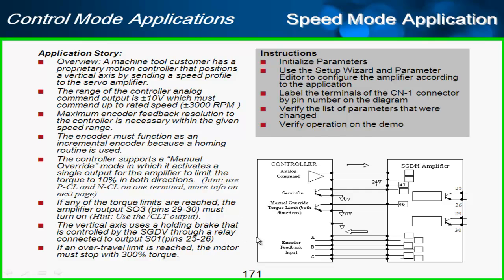This is a vertical axis that uses a holding brake, and we'll be controlling the holding brake through a relay connected to output one, pins 25 and 26. Finally, this is a vertical application, so if the motor hits an over travel we'd like it to stop with maximum torque and leave the motor enabled.